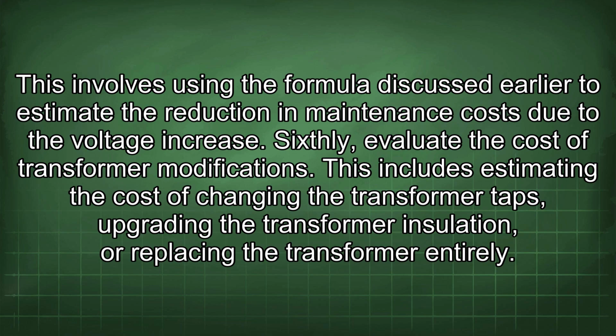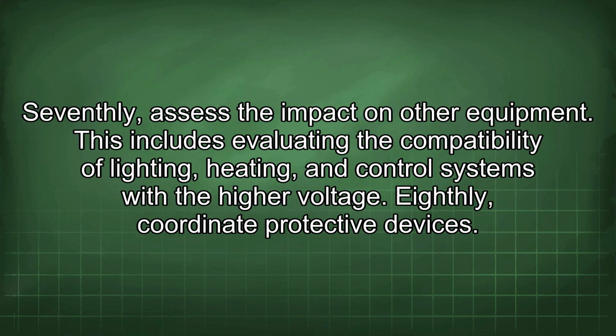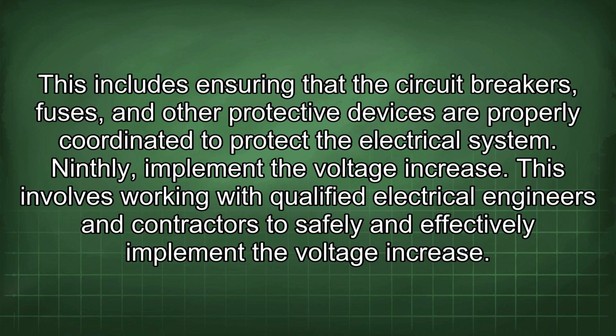Sixthly, evaluate the cost of transformer modifications. This includes estimating the cost of changing the transformer taps, upgrading the transformer insulation, or replacing the transformer entirely. Seventhly, assess the impact on other equipment. This includes evaluating the compatibility of lighting, heating, and control systems with the higher voltage. Eighthly, coordinate protective devices. This includes ensuring that the circuit breakers, fuses, and other protective devices are properly coordinated to protect the electrical system. Ninthly, implement the voltage increase.